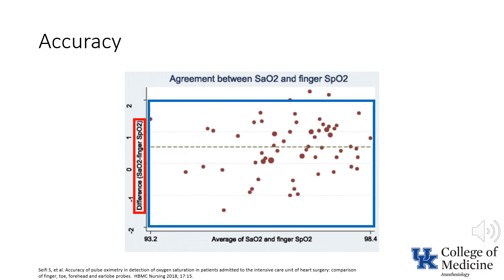As indicated by the blue box, essentially all of the values reported for SpO2 were within about 2% of the values reported from the blood gas. This is consistent with studies which have demonstrated that the SpO2 is within 5% of the value of arterial oxygen saturation measured by a co-oximeter. This relationship holds true for values of saturation between 70 and 100%.